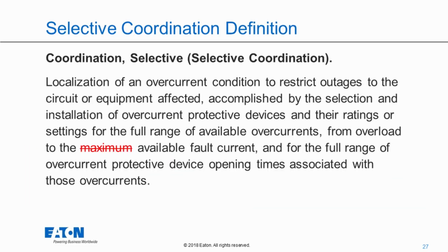If we look at the definition of selective coordination to further clarify what we mean when we use the term, the definition reads: it's simply the localization of an overcurrent condition to restrict outages to the circuit or equipment affected, accomplished by the selection and installation of overcurrent protective devices and their ratings and settings for the full range of available overcurrents from overload to the maximum available fault current.